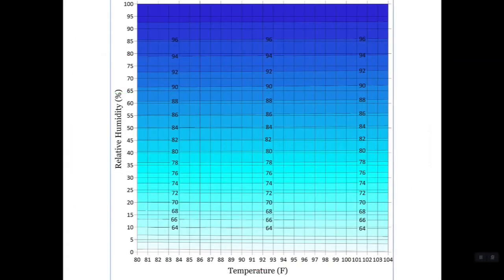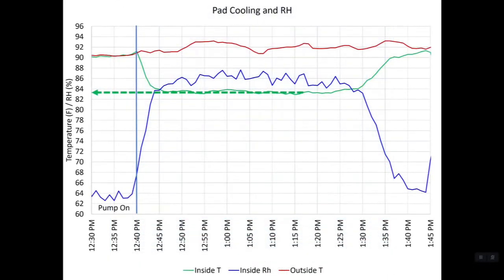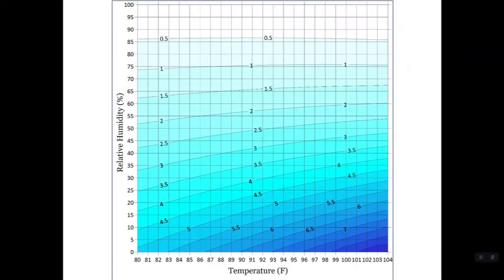What about the humidity? At 92 degrees, drawing a line up and over from 62 percent, we see the incoming humidity should be around 88 percent. In fact, the humidity was pretty close to that — around 86 percent — which is pretty good considering that the accuracy of most humidity sensors is plus or minus 2 or 3 percent.